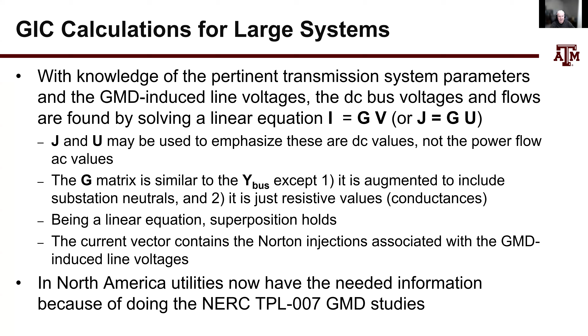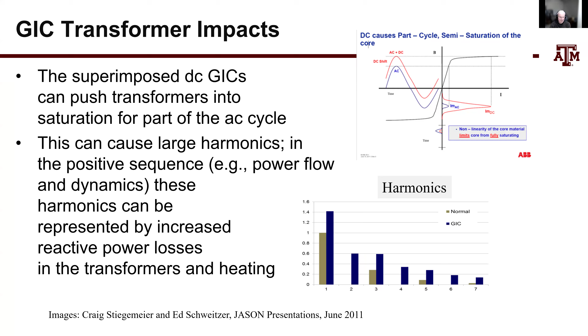Once we get the GICs, which are time varying, we look at what sort of harmonics are going to be induced in the transformers, which depends on the construction of the transformers. Those harmonics then increase reactive power loading and cause heating.